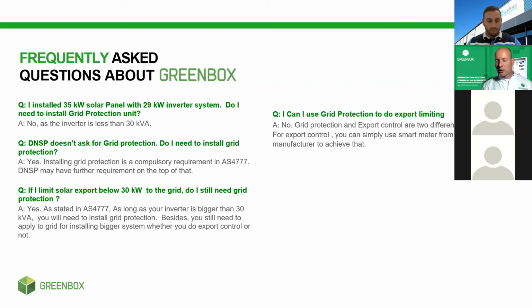Next one, I'll touch on that as well. If I limit my export down to 30 kilowatts or below to the grid, do I still need grid protection? The answer is yes. And the final one: can I use a grid protection unit to export limit? The simple answer is no. That is something that needs to be done through the solar inverters. The grid protection board cannot help you there.